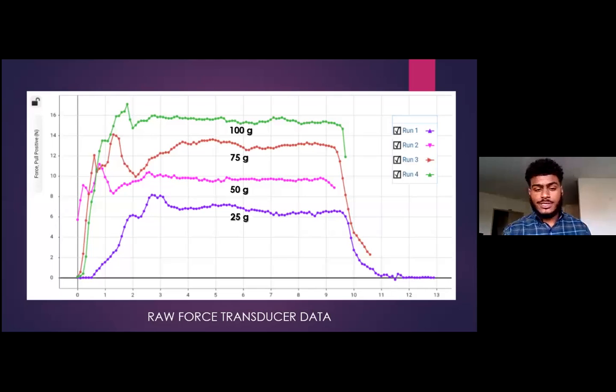Now, these are some raw force transducer data from just one angle specifically. Again, just to show you a visual of how this looked, this first purple line right here was at 25 grams. I took the recording for about 10 seconds total, and then we cut it off. We added 50 grams. We went back to that same angle. We took it again. We cut it off. We took the same measurement again for 75 and 100. And so we just increased about 25 grams for the force transducer, or the arm model specifically, and that's how we got these recordings.